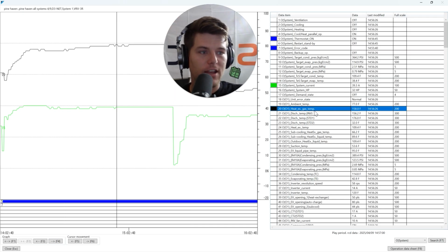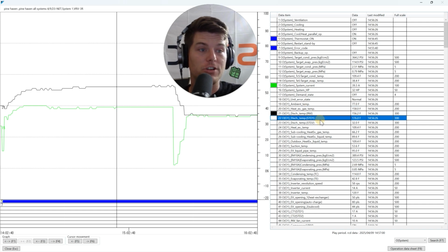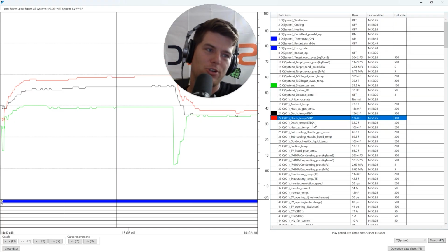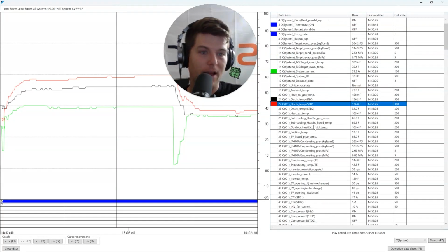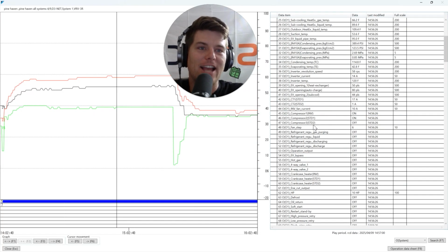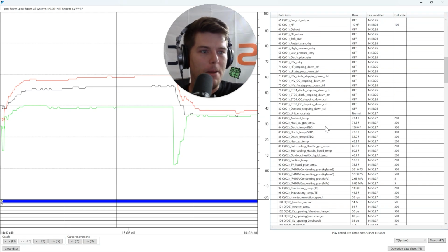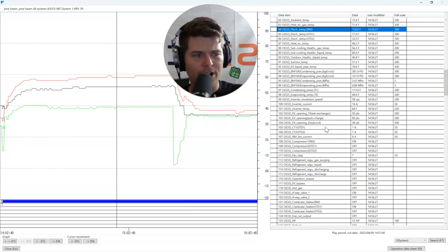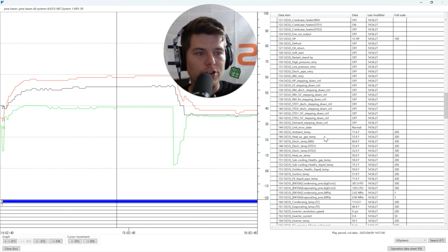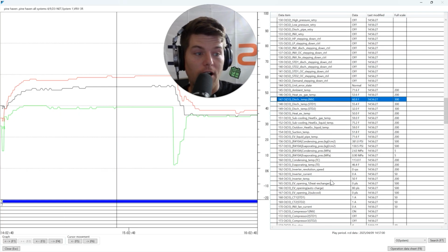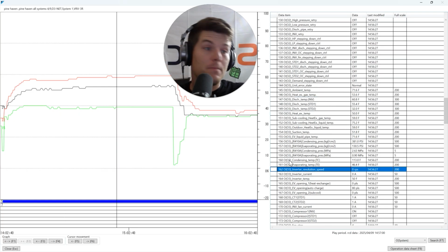Heat exchanger gas temp, right? 158. That's actually pretty good. Inverter discharge temp. This one's pretty high. Well, wait a minute, Roman. You said there's low discharge superheat. Okay, low discharge superheat. I'm not lying here, guys. Okay, I saw it. It exists. It's here. This one is pretty good. Let's look at the other module. It's probably off, and it is off. Okay, not a big concern here.